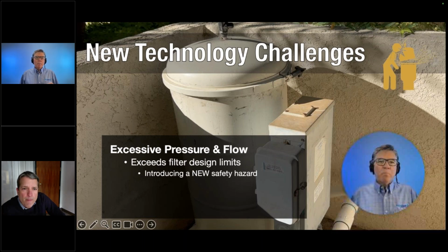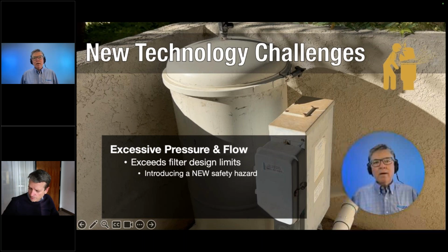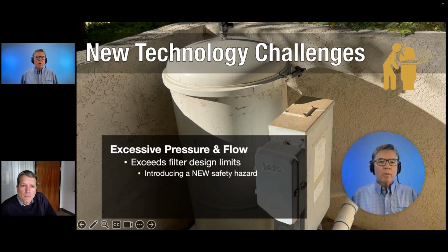The pressure side of this is something to be extremely aware of, especially if it's got older plastic tanks. Because the homeowner just needs a new pump, this is where you probably want to be more careful and look at what it is you're replacing. What does the equipment pad look like? What is the pipe size? What is this old filter? And you may want to go with, instead of a 3-horse, a 1.5-horse or a 1-horse, or even downsize.